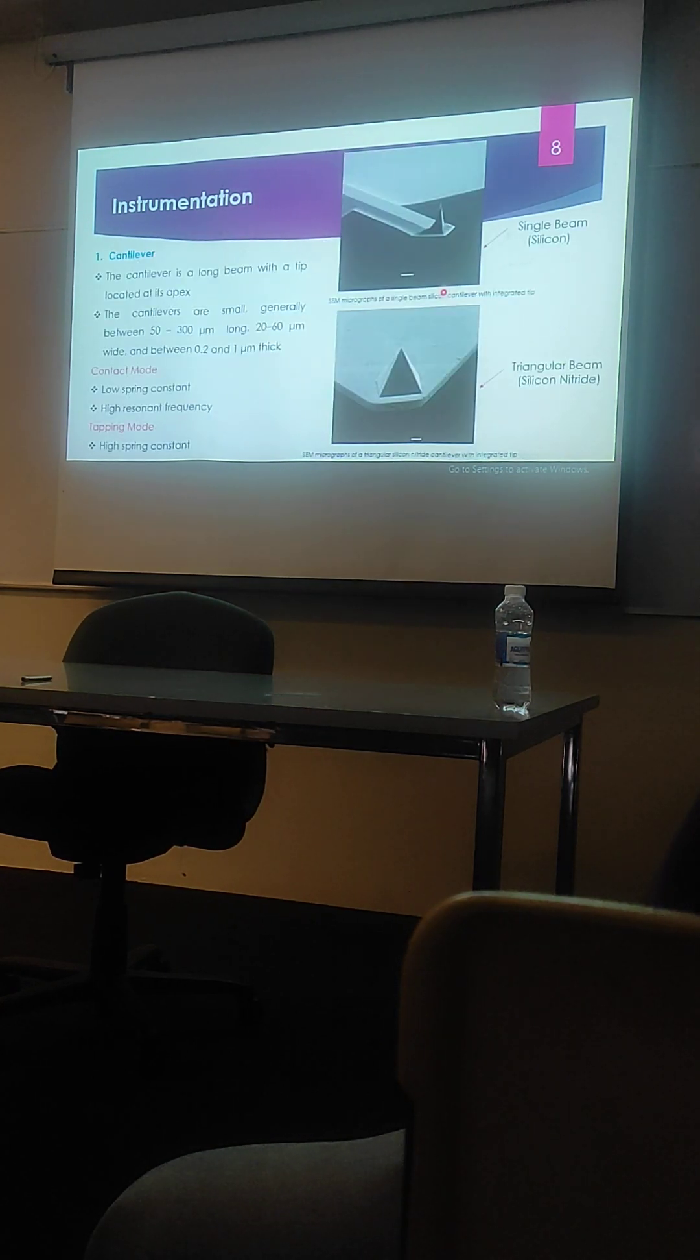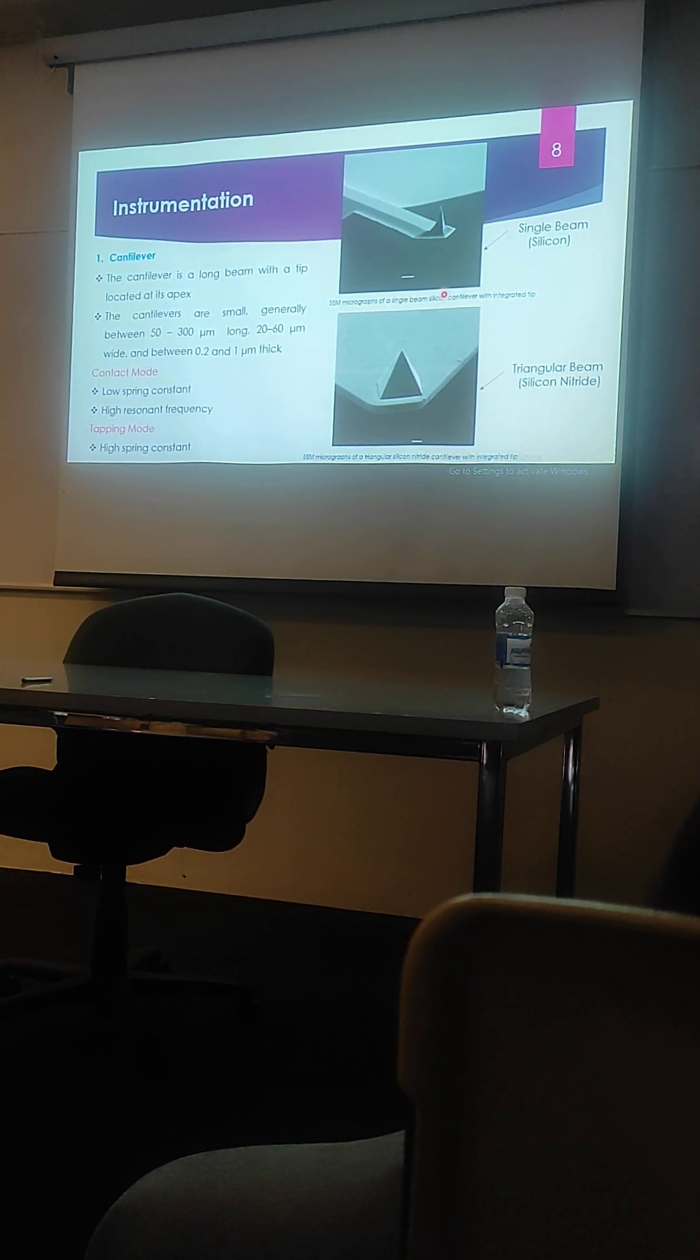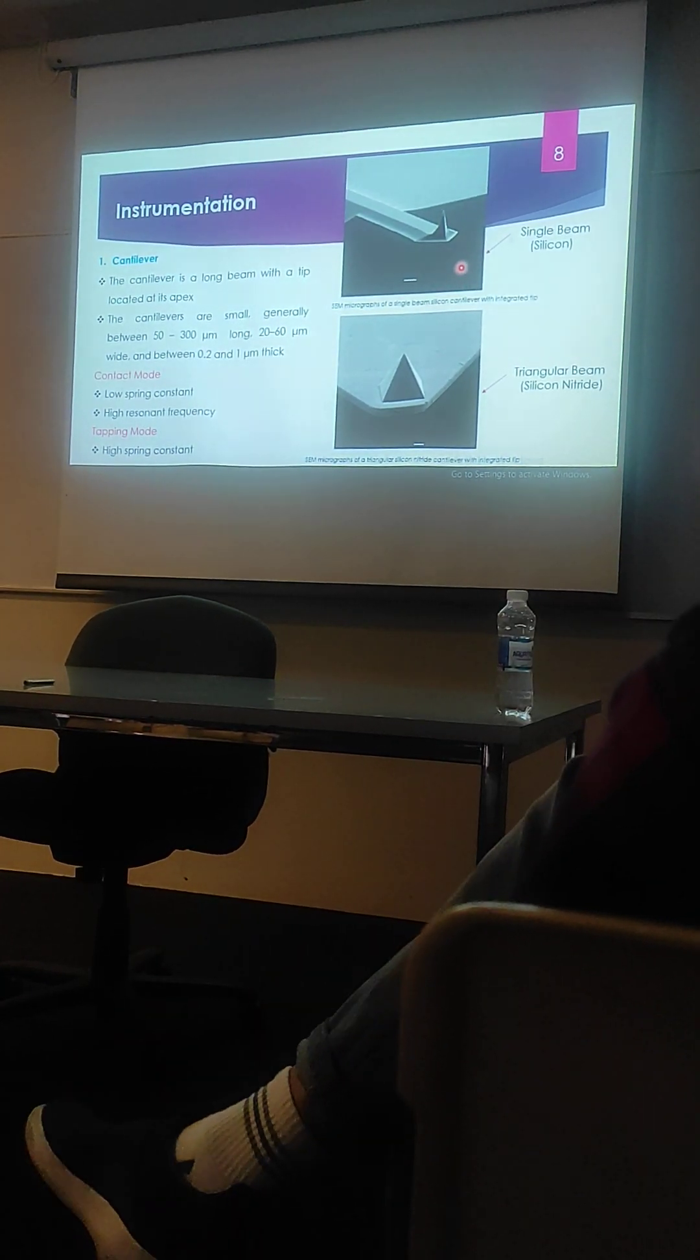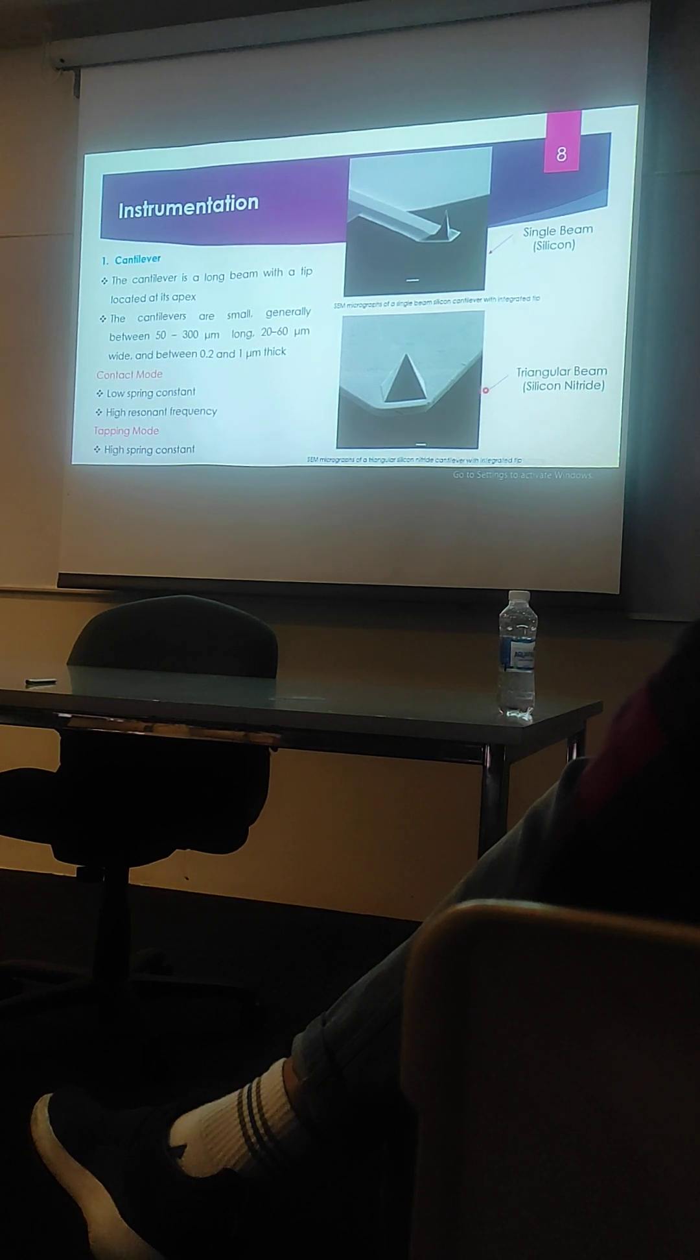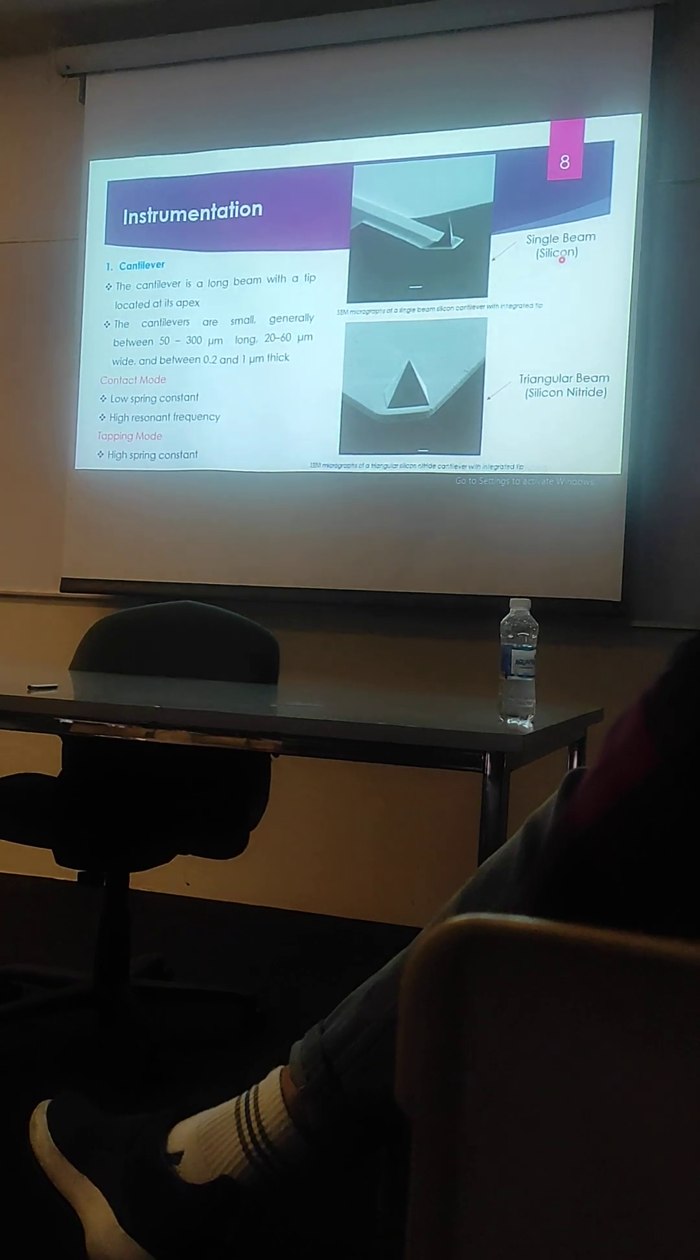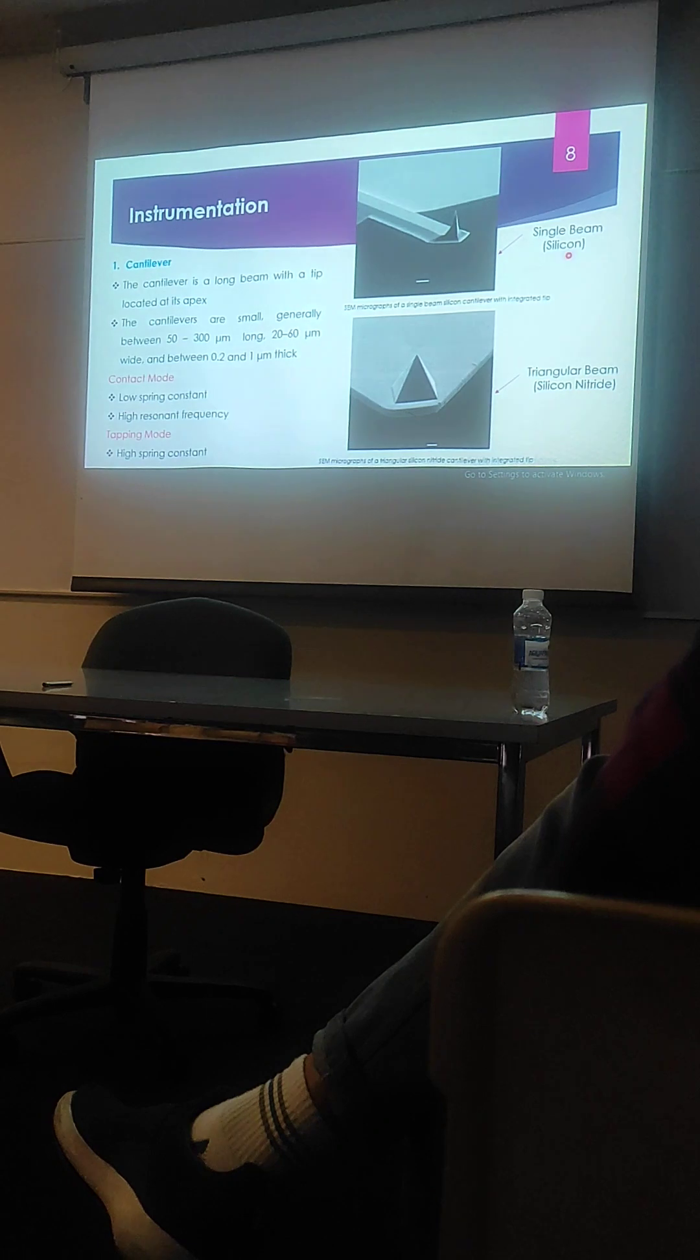Let me discuss these components in more detail. Cantilever is a long beam with a tip located at its apex. You can see two types of cantilevers that are generally used in atomic force microscopy. We have a single beam cantilever which is made from silicon and a triangular beam cantilever which is made from silicon nitride. This single beam cantilever is usually used in one of the modes of AFM, the contact mode.